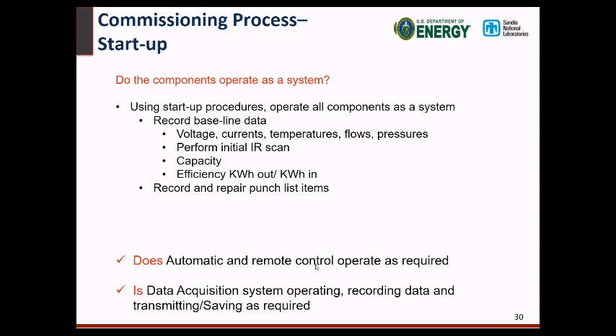You also want to do, if you do have a site controller or you're doing this remotely controlled to the system, you want to test that out, as well as just make sure the data acquisition system is recording correctly. Make sure you're not having some weird sampling problems or data is not being timestamped correctly.